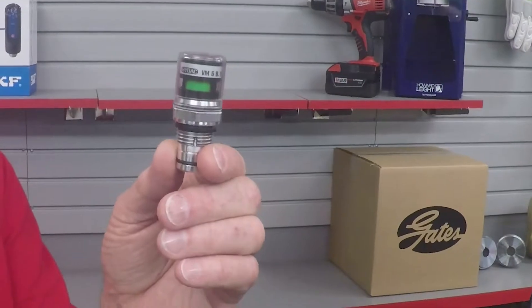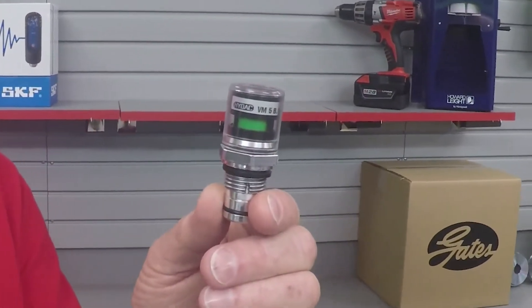How do you know when it's time to change the element? Rather than relying on a time period or waiting until the system goes into bypass, we recommend that you use a clogging indicator, which will let you know to what degree your filter is blocked at any time.